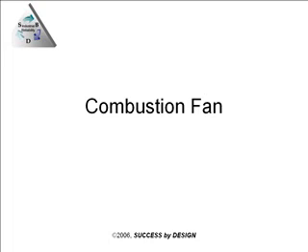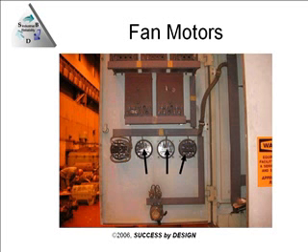This is a particular issue I've dealt with recently on an 800 horsepower, 1800 RPM machine. Now, these particular machines are located approximately 80 feet in the air, and we had to test them from the ground floor, and we had to take the data, because they were 4160 volt machines, from the back of the CTs.